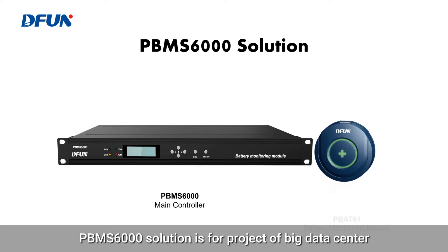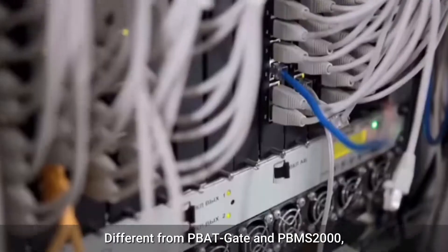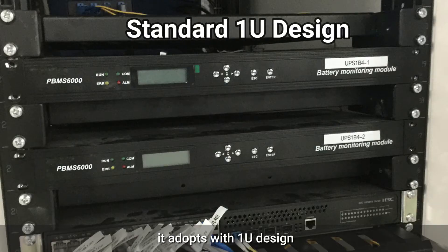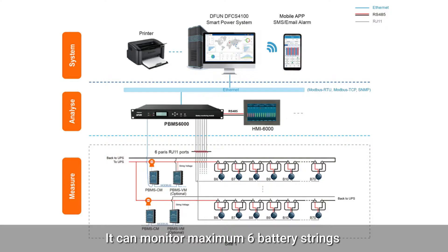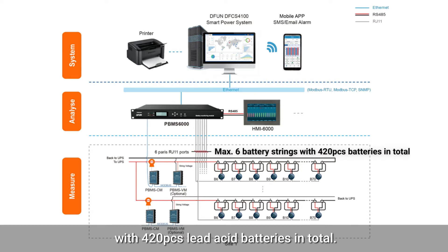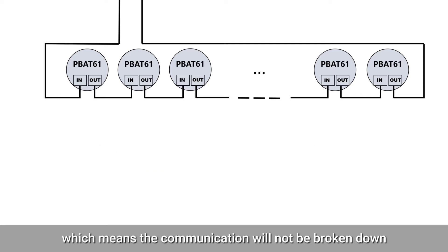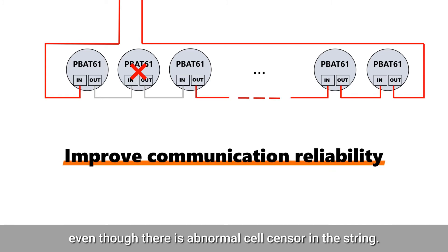The P-BMS-6000 solution is for projects of big data centers. Different from PBAT-Gate and P-BMS-2000, it adopts a 1U design which is more suitable for distribution cabinets. It can monitor a maximum of six battery strings with 420 pieces of lead-acid batteries in total. Also, the P-BMS-6000 is able to communicate in a ring topology, which means the communication will not be broken down even if there is an abnormal cell sensor in the string.